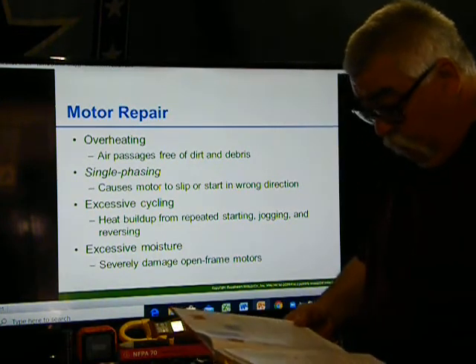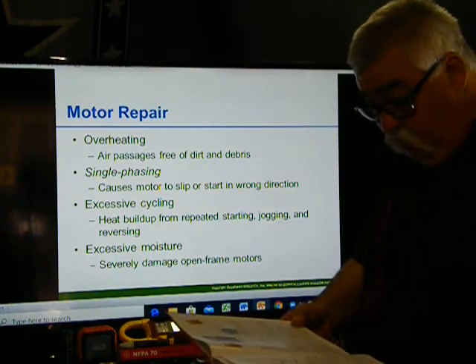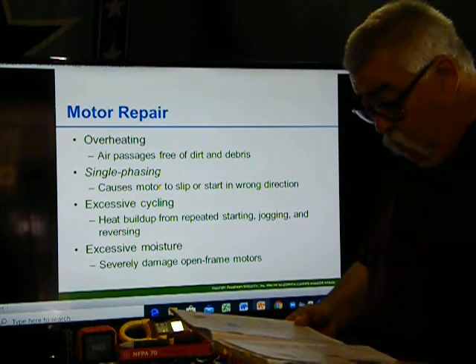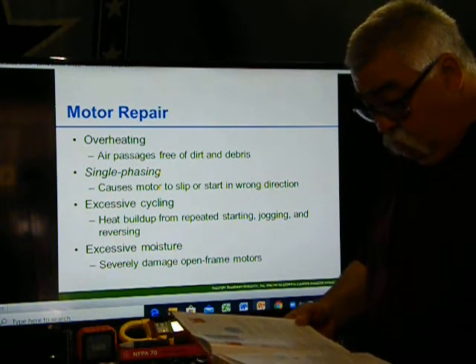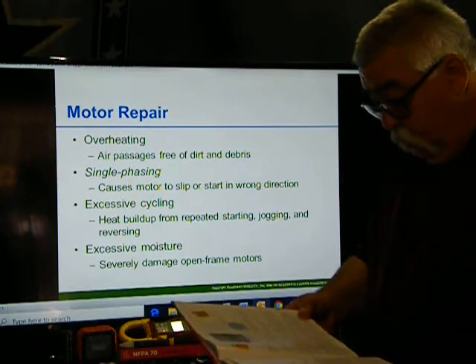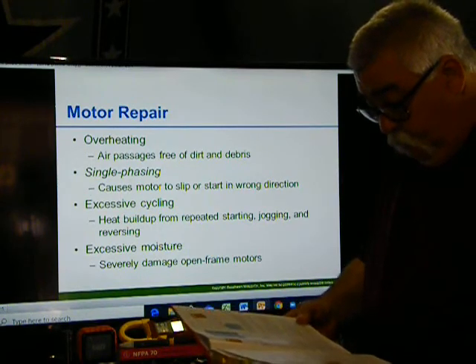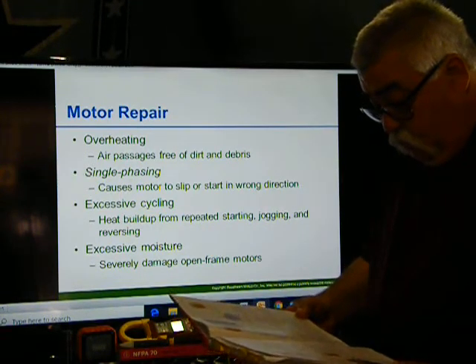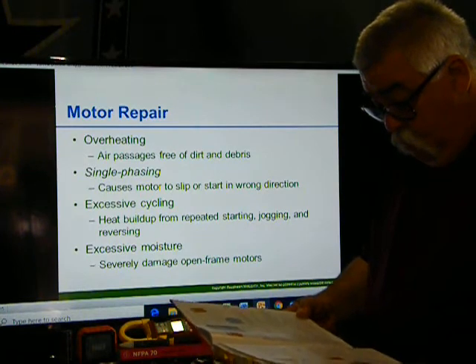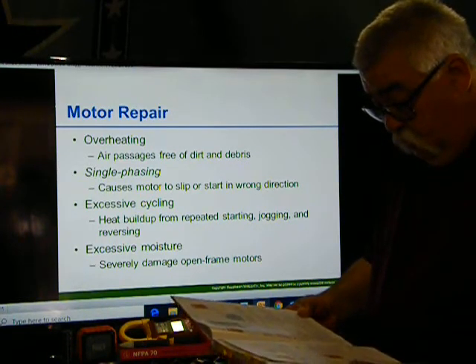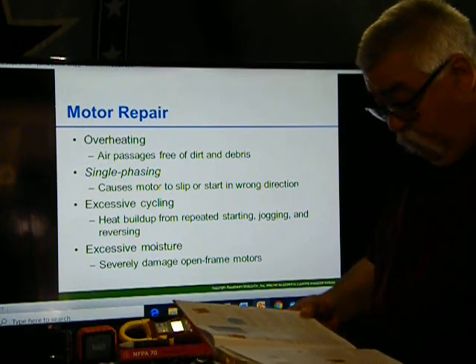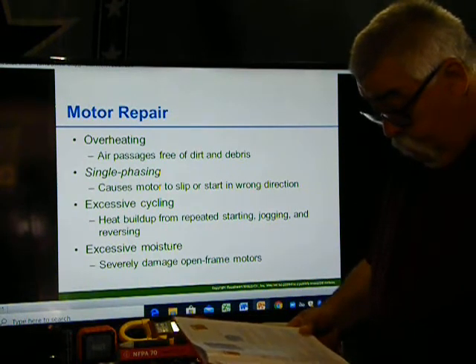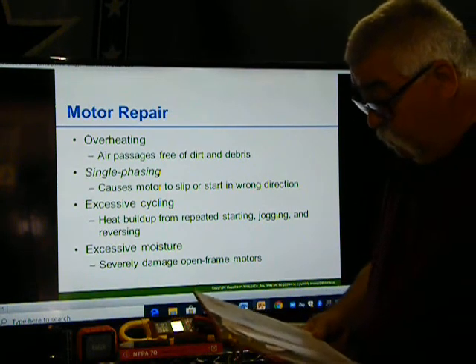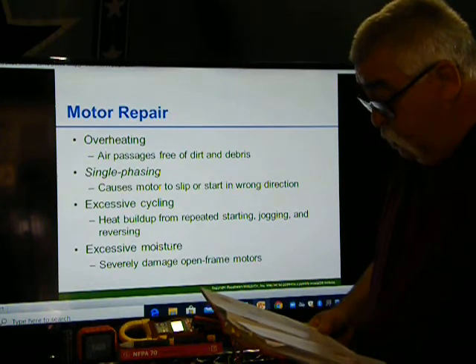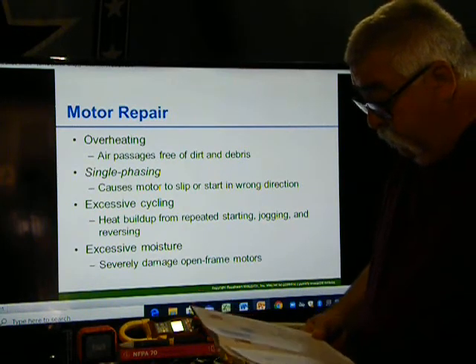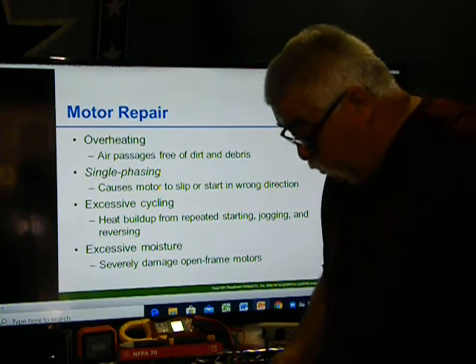A common cause for motor failure occurs when one phase of the three-phase power opens, leaving the motor running on the remaining two lines. This causes the motor to slip, which in turn creates heat and vibration. Sometimes single phasing occurs when the motor is not running. When the motor eventually starts up, it either starts in the wrong direction or simply vibrates and hums. To verify single phasing, measure each of the motor's phases to ground. Two values will be correct and one will be significantly different.